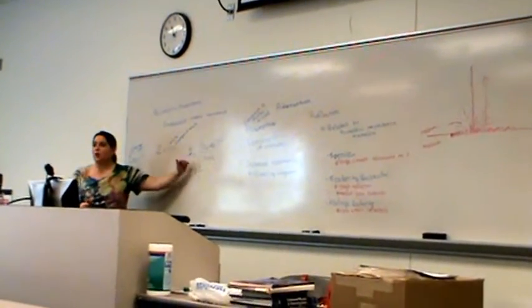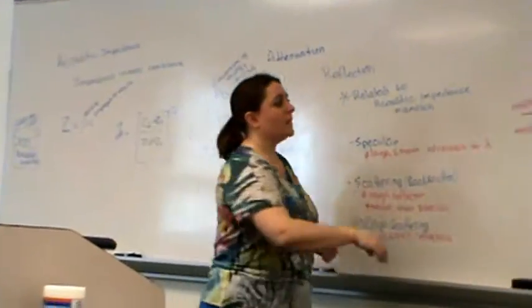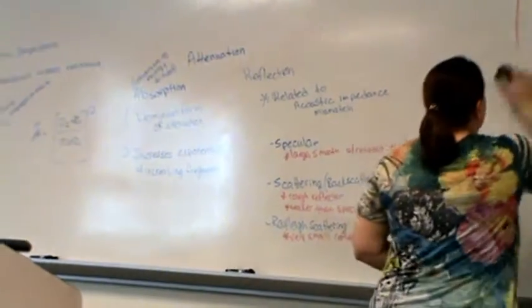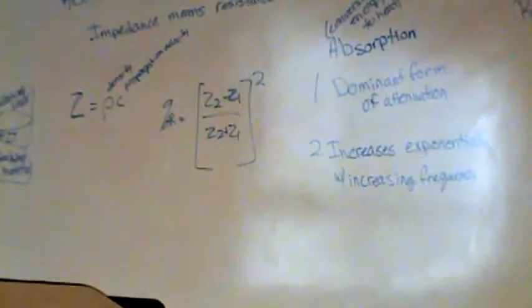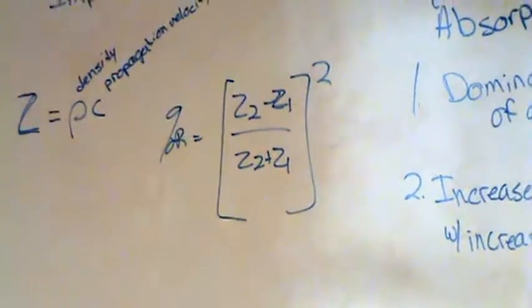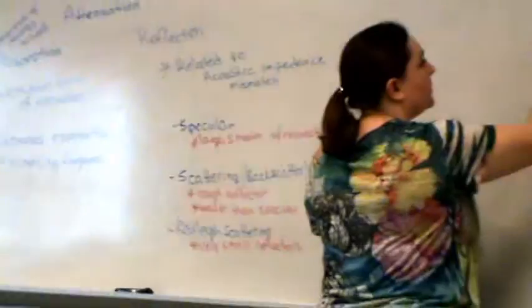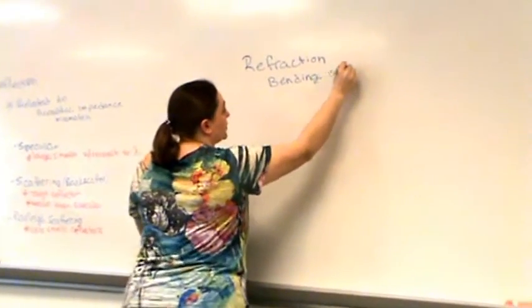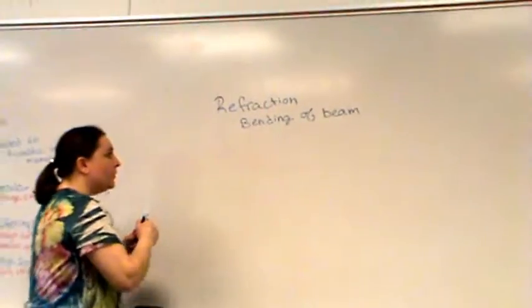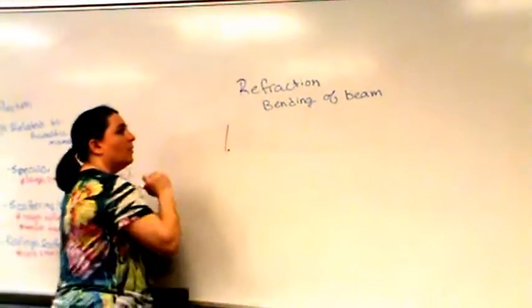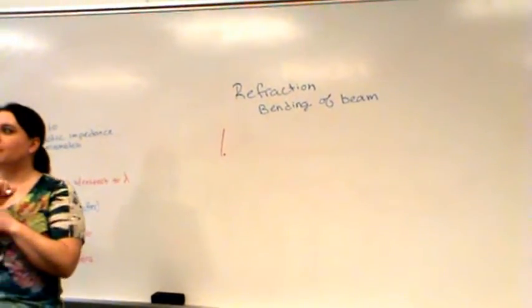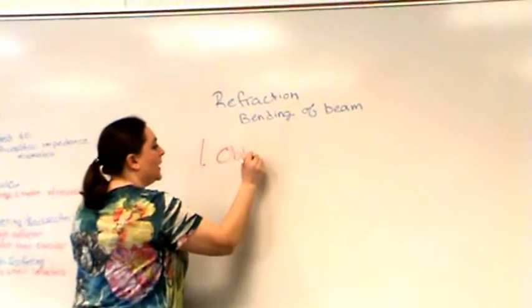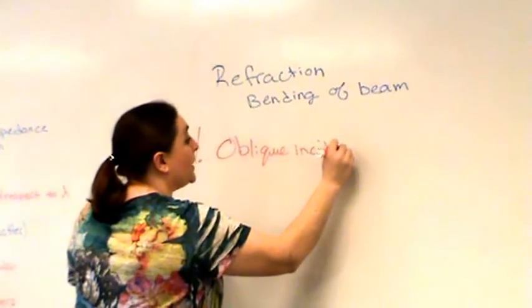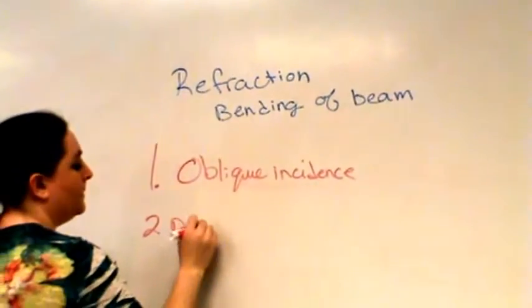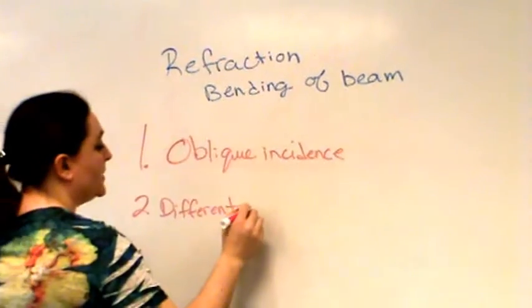So that's the idea of reflection. Remember, reflection is always about this acoustic impedance mismatch. That's always what it's about. In order to determine what kind of reflection we have at all, we have to know what that acoustic impedance mismatch is. Versus refraction. Refraction is the bending of the beam, so the beam is no longer traveling in a straight line. And it has two components that have to be present in order for it to occur. What are the two things that have to be present in order for refraction to occur? Oblique incidence, and different propagation velocities. So this is different than an acoustic impedance mismatch.